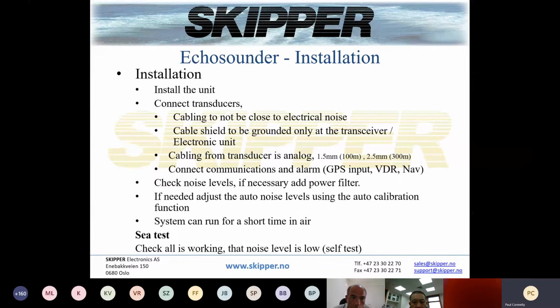When it comes to installation, the first thing is to install the units and connect the transducers. The cabling should not be close to any electrical noise. You need a shielded cable, and it should only be grounded at the transceiver, not at any junction boxes along the way. The cabling to the transducer carries analog signals, so the same rules apply as with the GPS systems: 1.5 millimeter cable up to 100 meters, and 2.5 millimeter screened cable up to 300 meters.